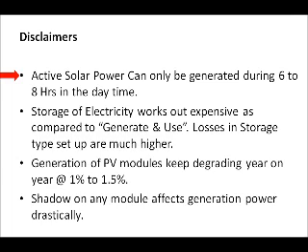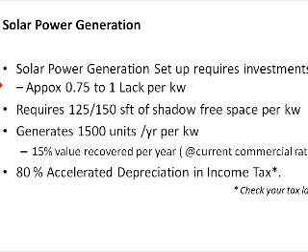Key technical notes: active solar power can only be generated for 6 to 8 hours a day. Storage of electricity is expensive, so the best approach is to use solar power in generate-and-use mode. Similar to batteries, the generation capacity of solar panels keeps degrading by 1 to 1.5% per year. The entire area of solar panels should remain shadow-free from 9 AM to 4 PM, or your generation will be drastically affected.